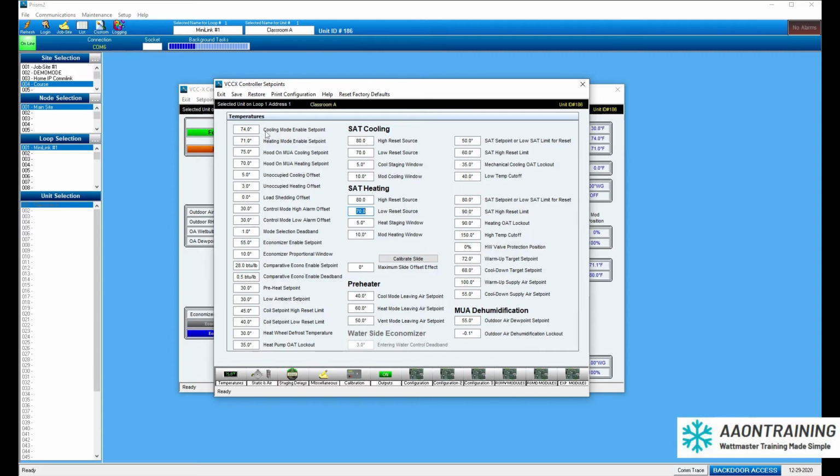So for vent mode, that's already been discussed. It's the space between here after it's crossed over the deadband threshold. So the deadband happens at the bottom and the top of here, but it also happens in the middle. So basically after it rises up the deadband above here, so let's say if it hits 72 or 73, it will shut off and go into vent mode.